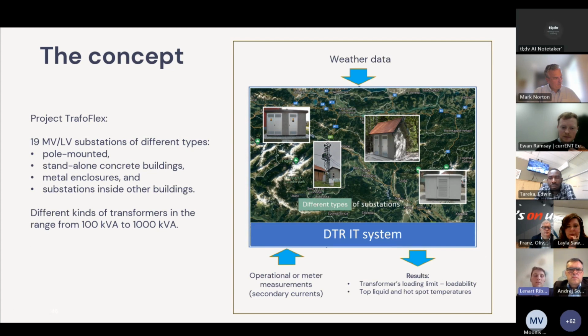So our concept was to deploy DTR calculations to 19 medium voltage to low voltage secondary substations of different types, meaning pole mounted transformers, standalone transformers, metal enclosed transformers, and substations inside other buildings. We implemented this on different kinds of transformers, in the range from 100 kilovolt amperes to 1000 kilovolt amperes. On the right side, we can see short representations. The pictures show all four different types of substations.